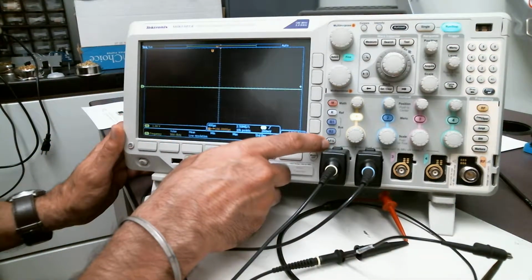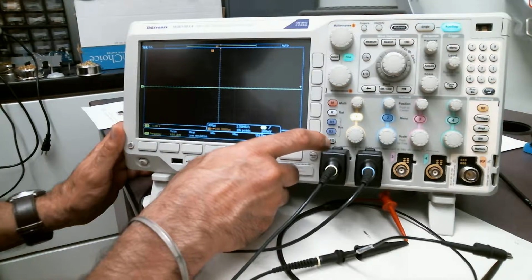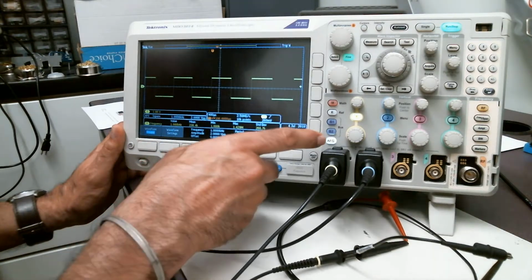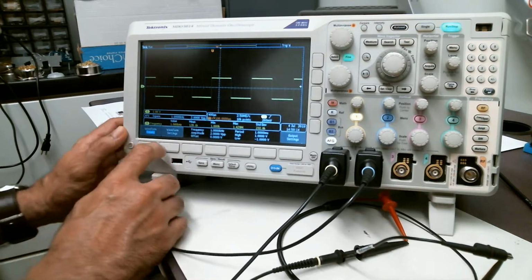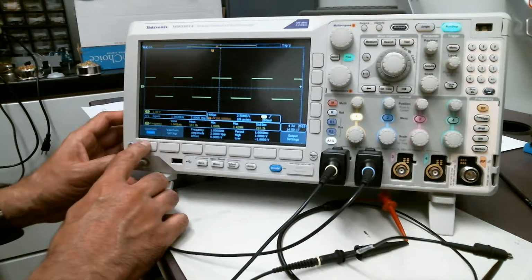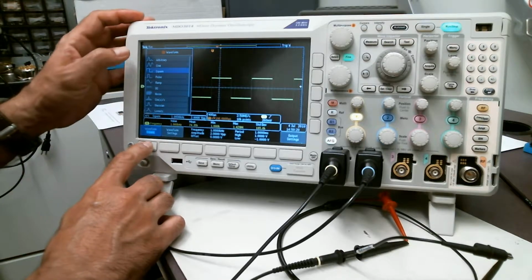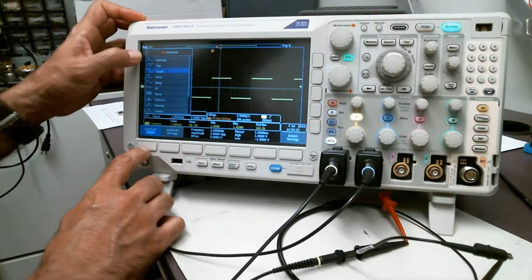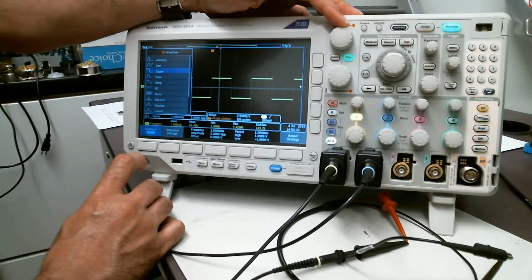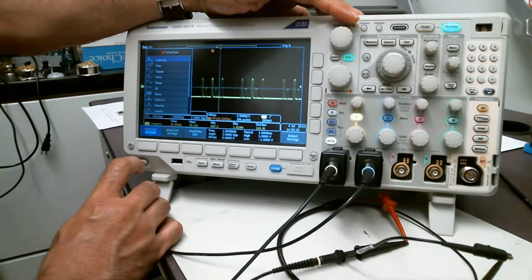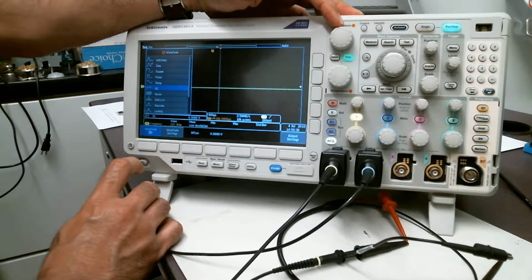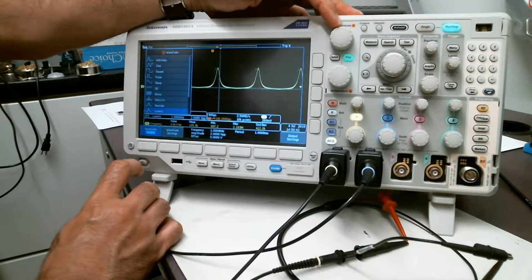So the AFG button is here, right on top of probe 1. I will press that, and it will turn on whatever the waveform was previously set last time. Last time somebody was using a square wave, and to change to any other wave, you can press this option button, and using this multi-purpose knob, you can select ramp, pulse, square, sine wave, arbitrary signals, etc. You can also apply a DC level if you need to, or noise for that matter, and some other functions which I have not used a lot myself. So you can explore these things.